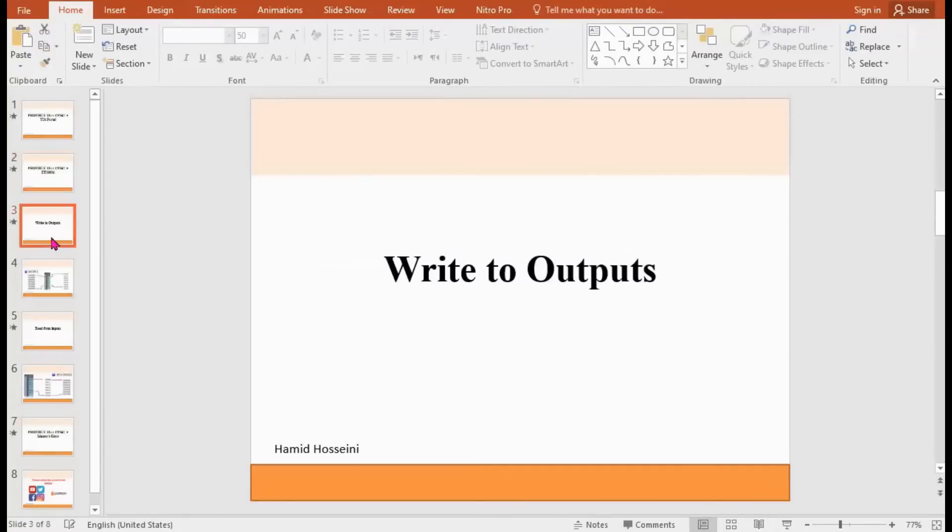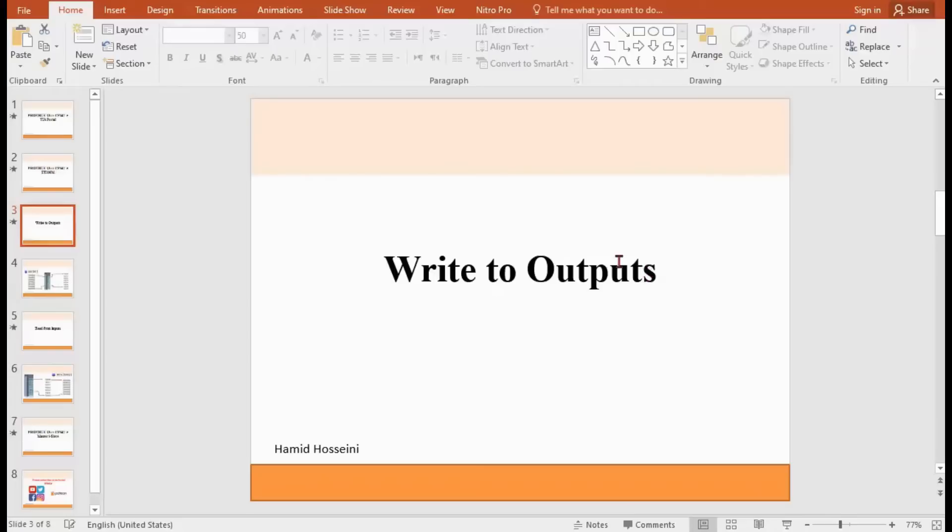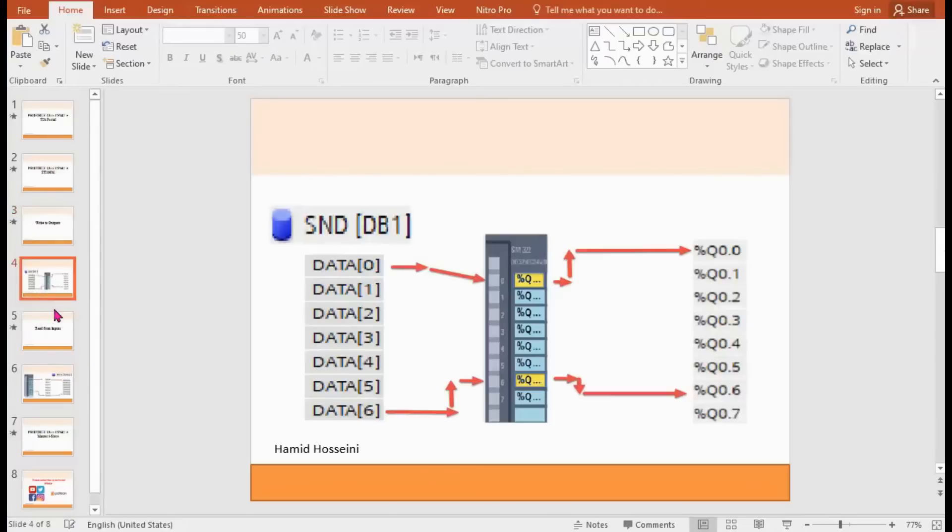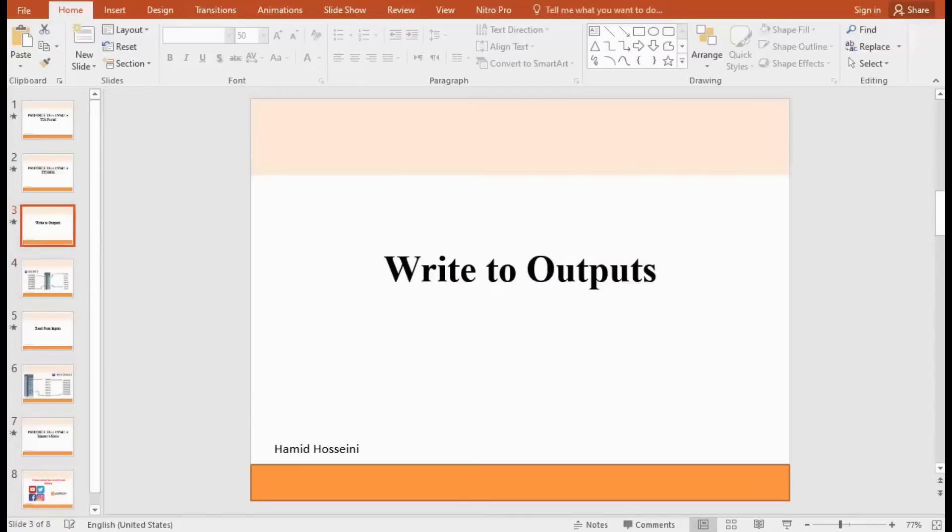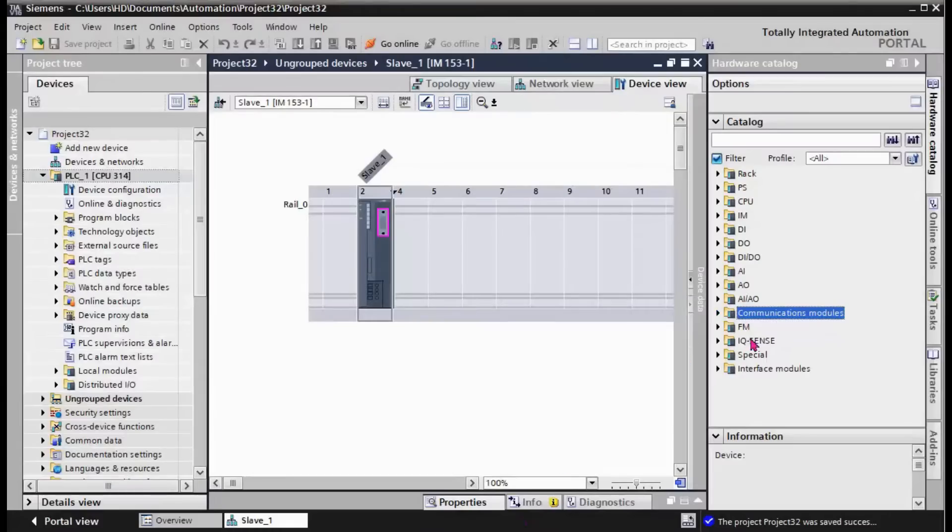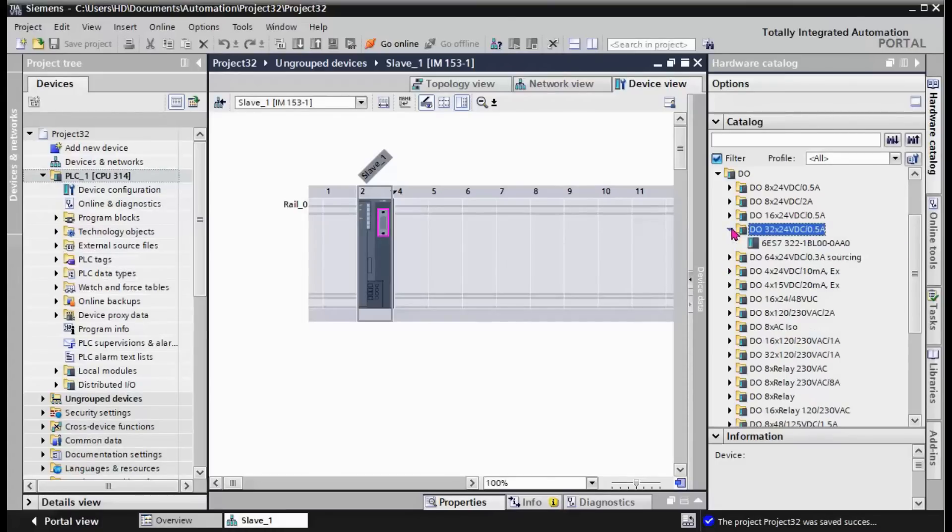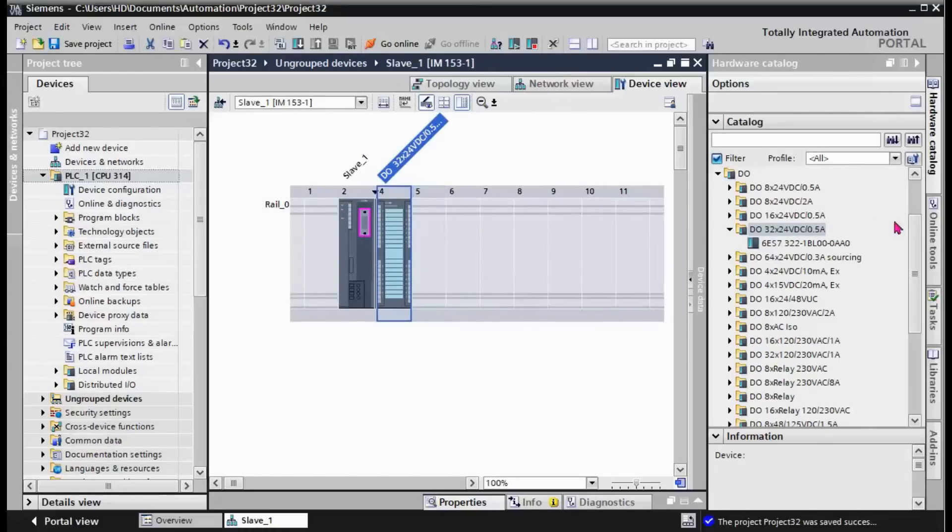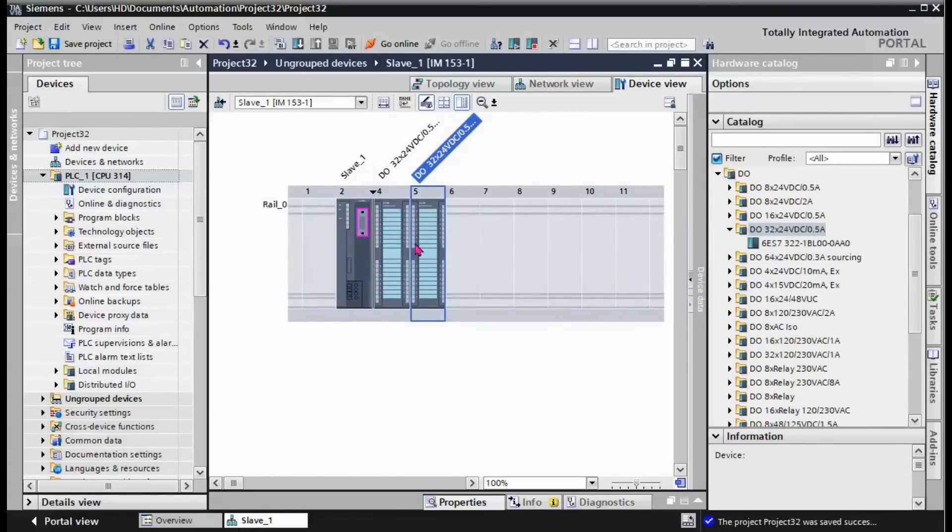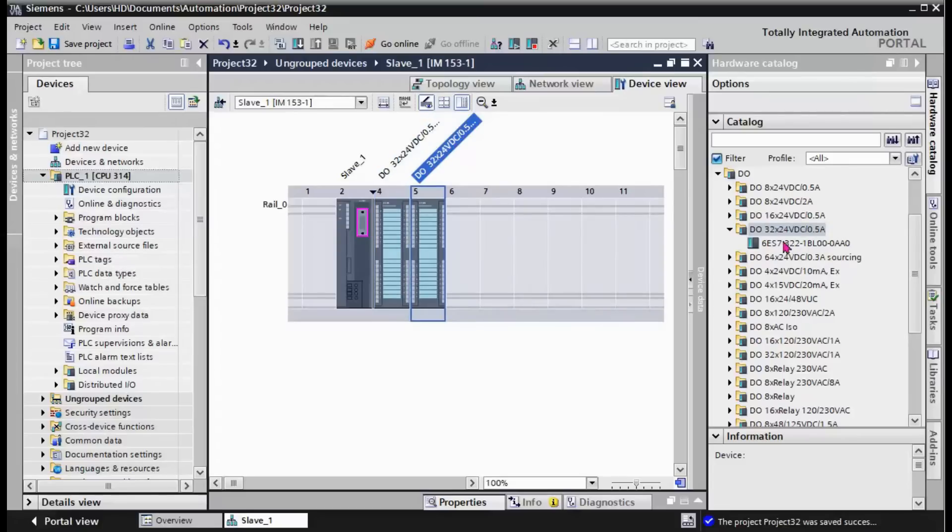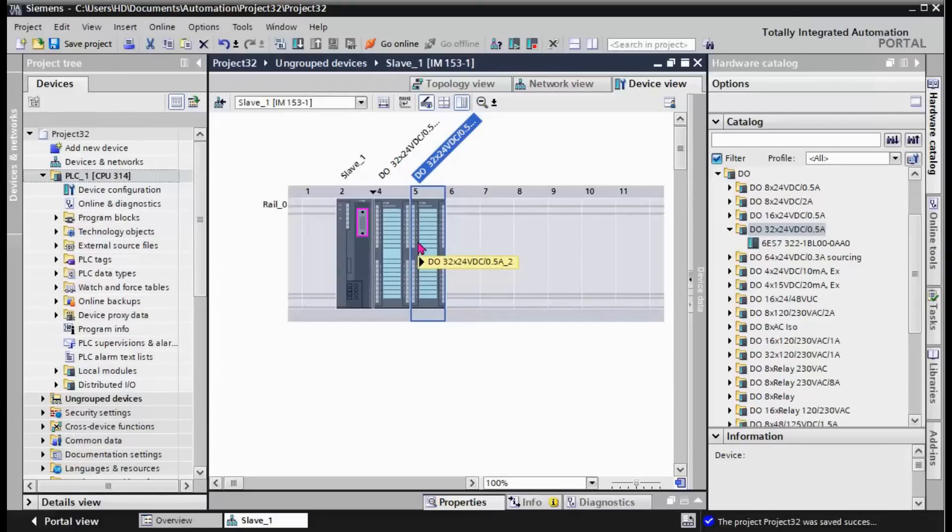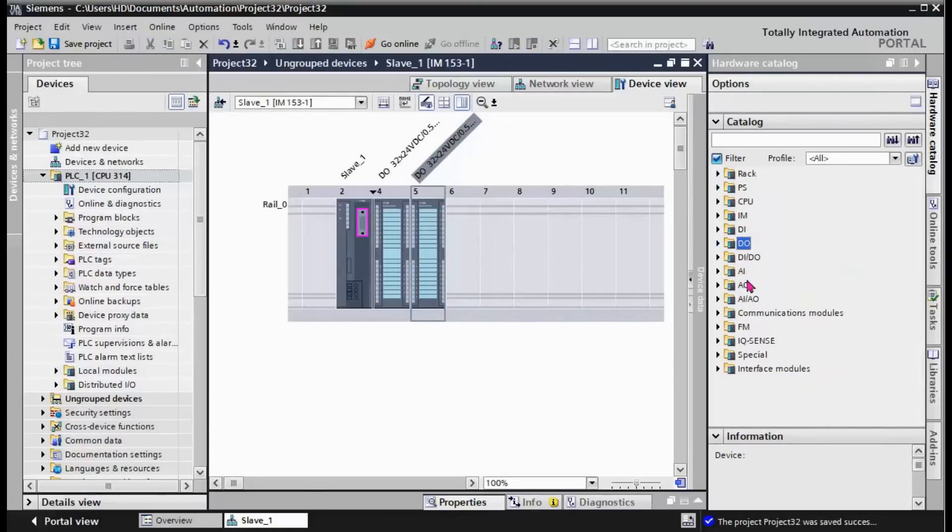The next step is to add the devices on the ET 200M. Based on our project, we need to write some values into outputs and read some values from inputs. In our design, we should insert digital outputs first. I select this digital output and put two modules nearby each other, 32 digital outputs.